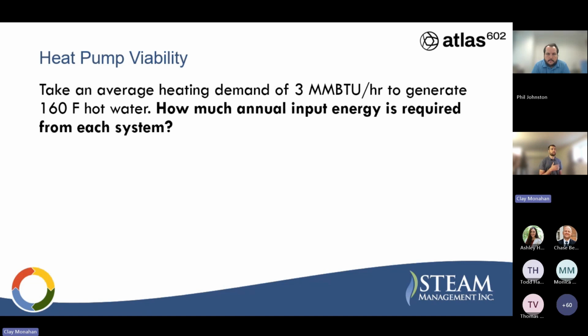Okay, so let's go through some different examples here just to see how the energy prices and the heat source temperatures affect system viability. So if we have an average heating demand of 3 MMBTU per hour to generate 160 degree F hot water, let's look at the annual energy input required for each system. 3 MMBTU per hour, that's a fairly significant load. For some folks on this call, it might not be that big. For others, it might be pretty sizable. But this might look like something like a CIP system, especially at that 160 degree mark. This could roughly look like that for a food processing plant or just domestic hot water. This fits within those parameters, just to kind of put it in terms of what your facility might look like.